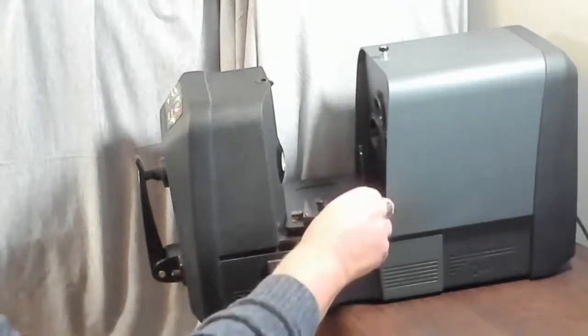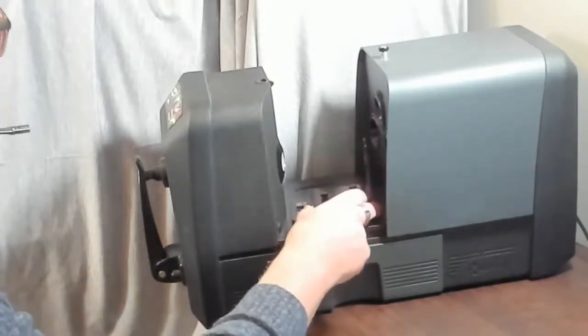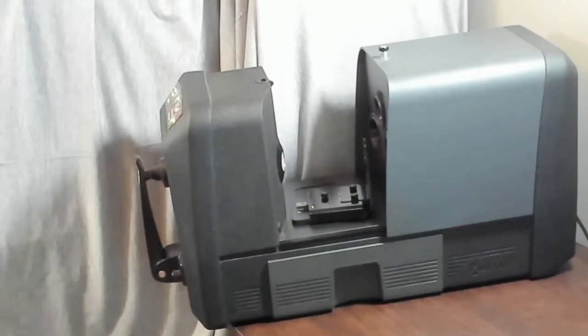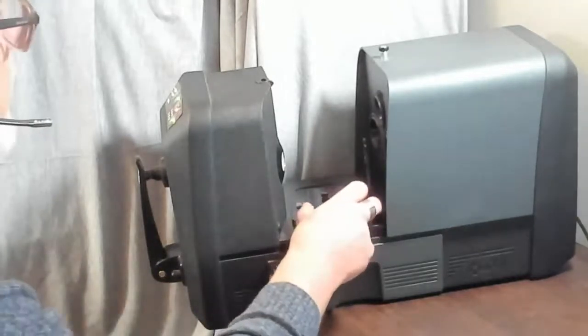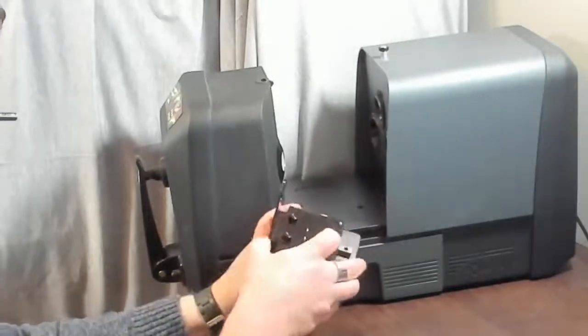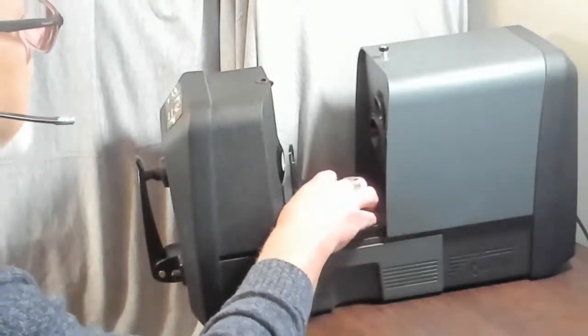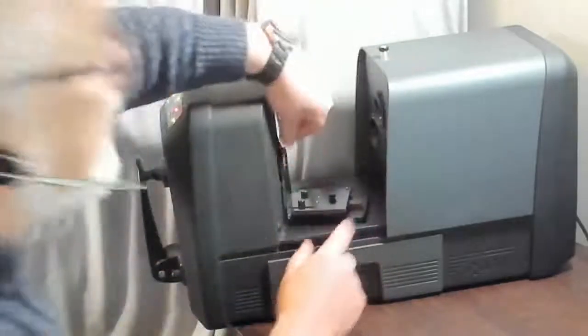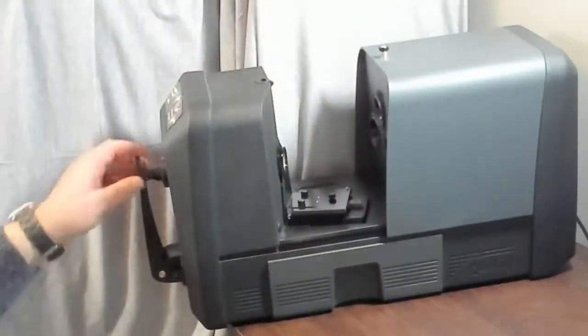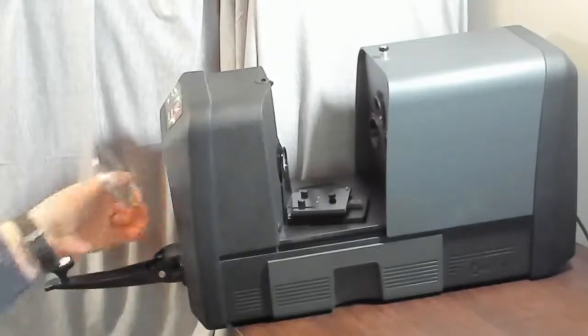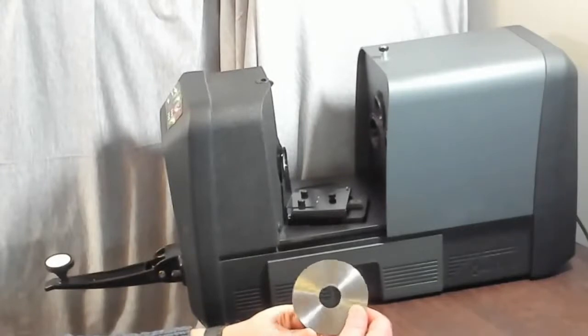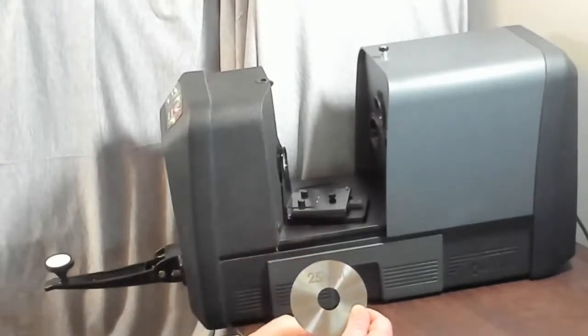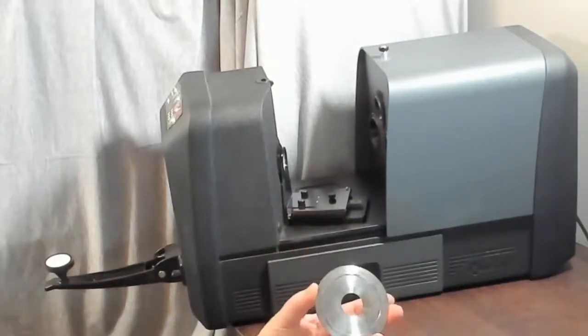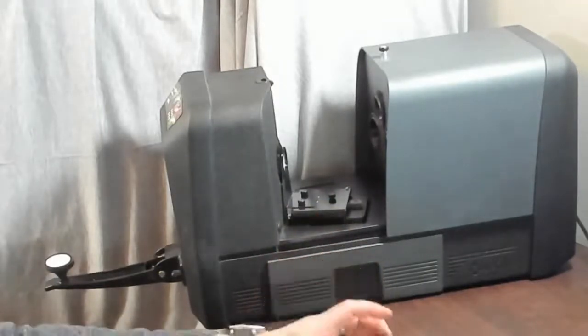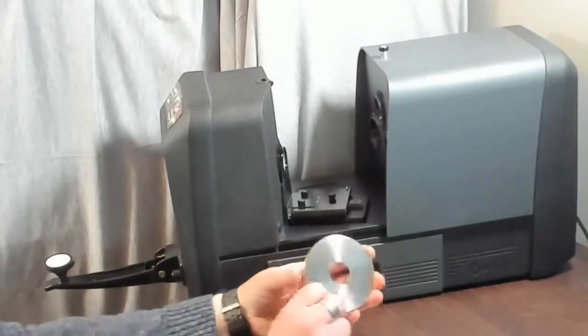Now, if I were going to be doing direct transmission measurements, I would line the pins up and slide them into place. There's a magnet there that holds it, and the device would be ready to do direct transmission. I, however, am going to be doing total transmission, which means I've got to put the sample up by the sphere, not by the optics. And so I have to slide that around and get it to position properly where it belongs up against the sphere. So that's all set. Next, we're going to replace the aperture plate. So this is the 25 millimeter aperture plate for reflectance, and I'm doing 25 millimeter transmission. You'll notice the transmission plate is silver on the back, just like it is on the front, whereas the 25 millimeter reflectance plate is actually white.